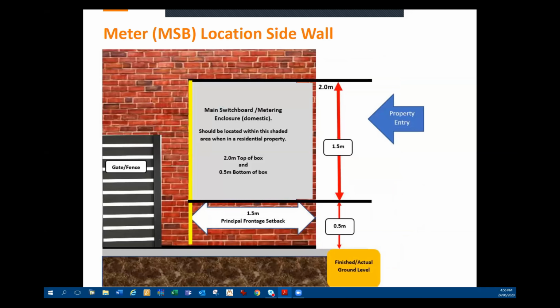With a meter main switchboard location on a side wall, so this is generally for a domestic installation, we try to give a bit better drawing on where the main switchboard is to be located. So basically, as long as it's within 1.5 metres of the front facing wall, so part of the principal frontage setback, that should be fine. And we've reduced the height of the bottom of the box to 0.5 of a metre to the bottom of the box and 2 metres to the top of the box.